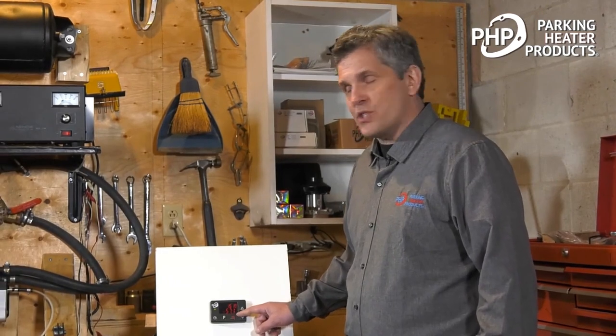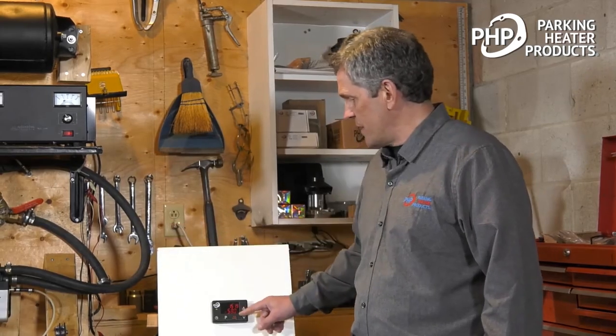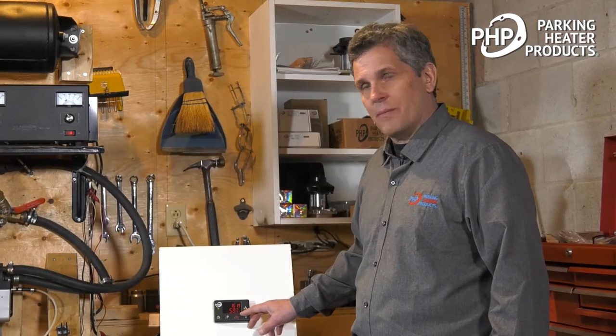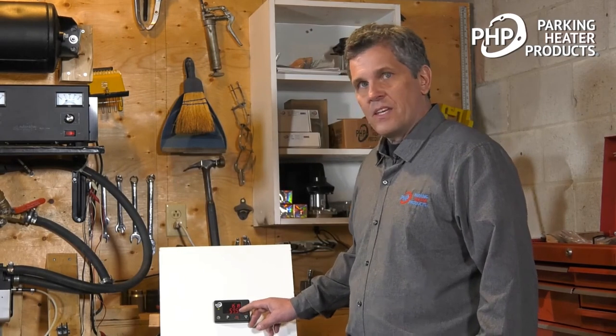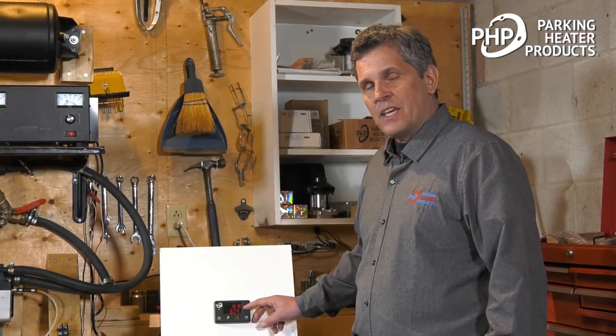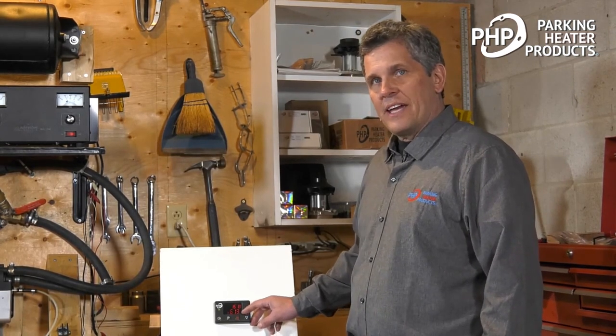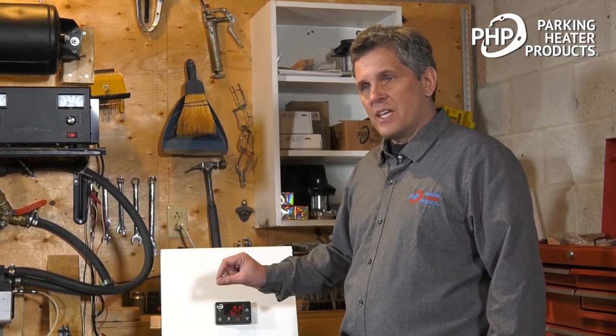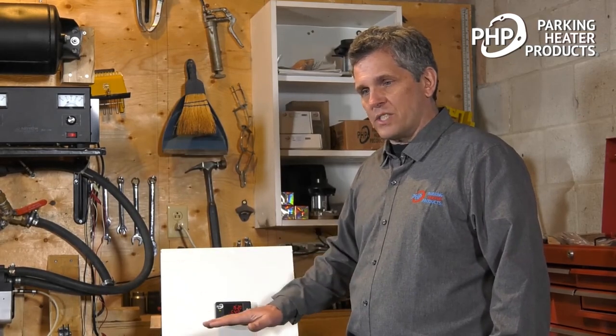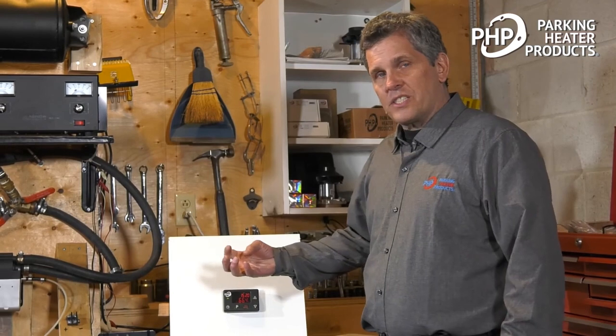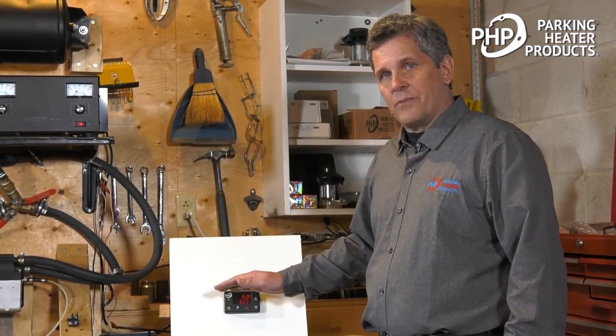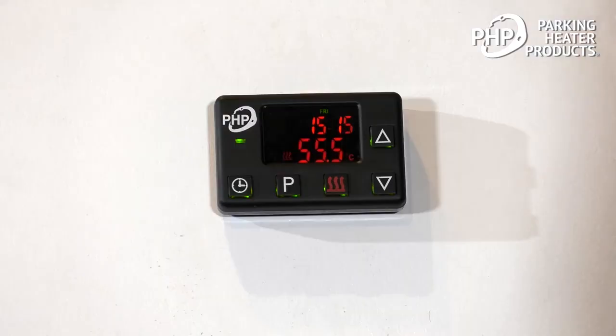The heater does monitor the temperature. It has a temperature sensor integrated into the heater, and the temperature is monitored here. That's the incoming temperature. It's currently showing 59 degrees. The heater will continue to run in high heat mode until the temperature reaches 70 degrees centigrade. At that point, it's going to switch into a low heat mode. The fuel pump pulses will slow, the blower motor will slow. If the temperature continues to rise, once it reaches 75 degrees, the heater will switch off and go through a cool down. If the temperature drops below 65 degrees while the heater is running in low, it'll kick back up into high. If the heater does reach the 75 degree level and switches off and cools down, it won't restart until it hits the 55 degree temperature.